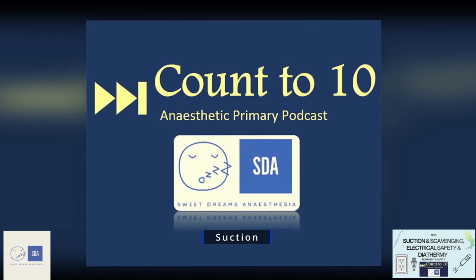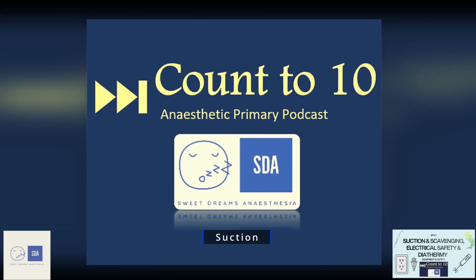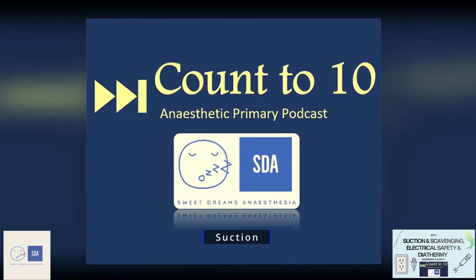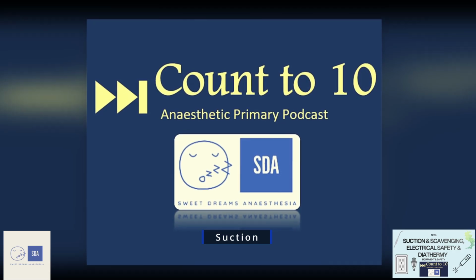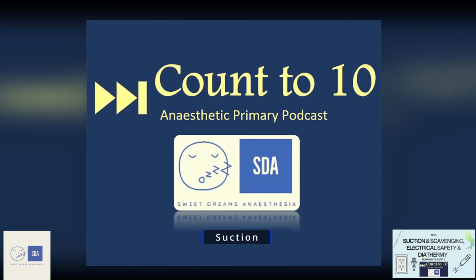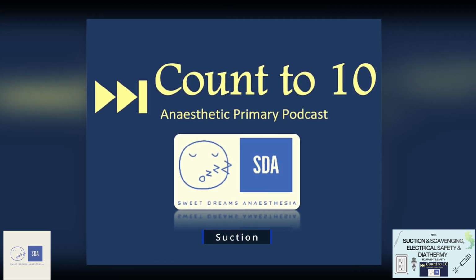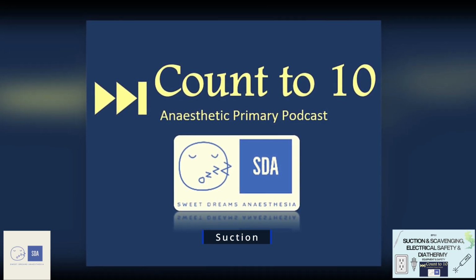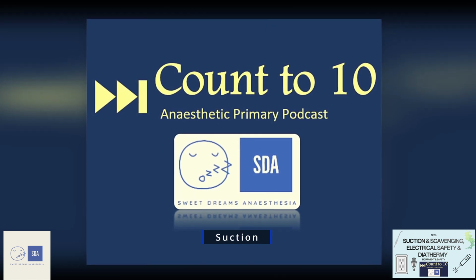So what are the principles behind making sure a suction device works appropriately? For this we go back to our three essential components. Firstly, looking at the vacuum itself. Vacuum is just an interchangeable word for negative pressure, and for a suction device you can have many sources of vacuum. A vacuum can be generated through electrically powered mechanical pumps, gas-powered pneumatic pumps, or manual pumps. Within the operating theatre itself, the suction is generated through an electrically powered mechanical pump.